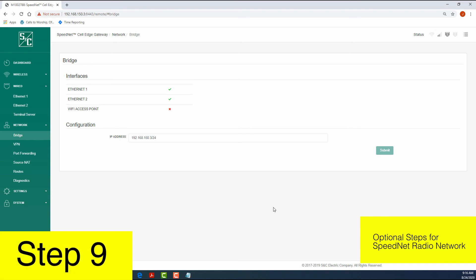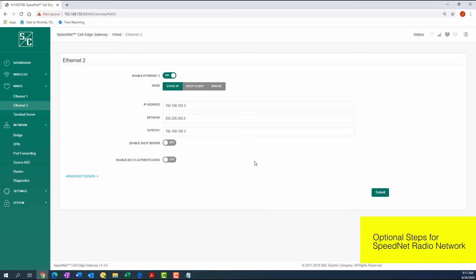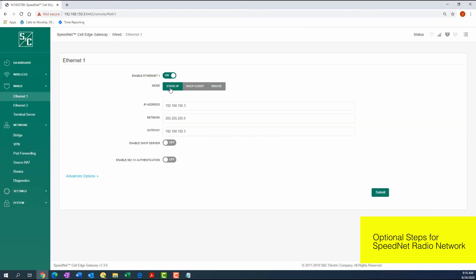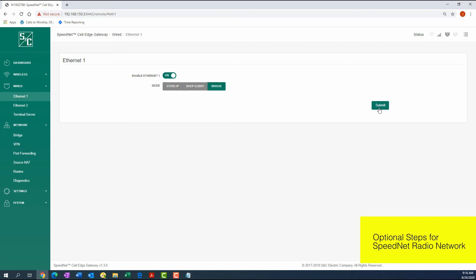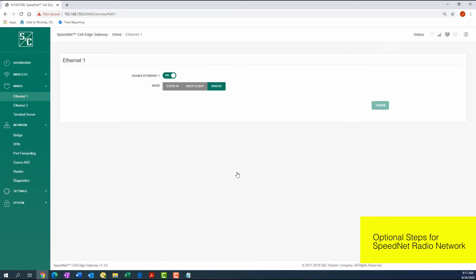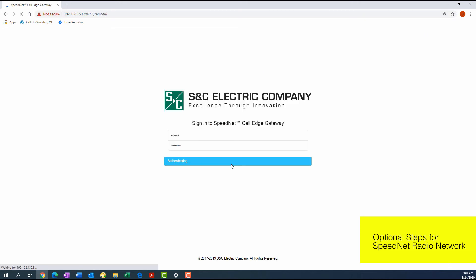Step 9: Navigate to the Wired tab and access the Ethernet 2 screen. Change the Mode setting to Bridge and click Submit. Make the same change on the Ethernet 1 screen. Note that the change in IP address will interrupt communication between the PC and gateway. Using the new IP address of the bridge, access the gateway login screen and log in to the gateway to continue with the configuration procedure.